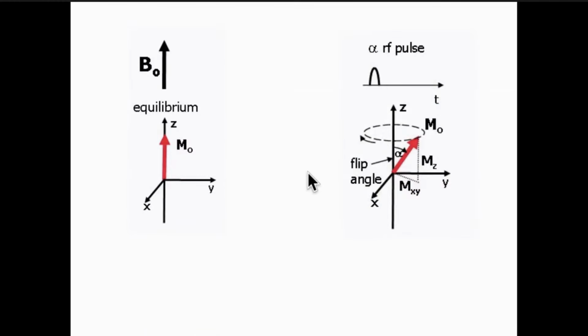And the strength of the radio frequency pulse that we applied is referred to as the alpha of the RF pulse, or oftentimes referred to as the flip angle. So if you look on an MRI sequence or MRI scanner, one of the parameters that you can set is what's called a flip angle. And that's just saying how much radio frequency pulse energy do you want to apply to cause the protons to go from the upright state to a certain deflection into the transverse plane.